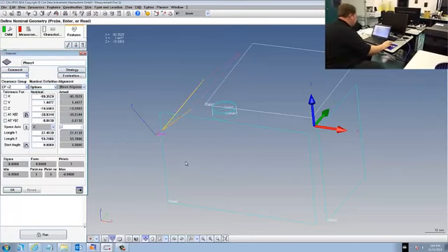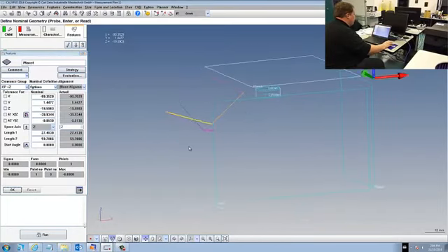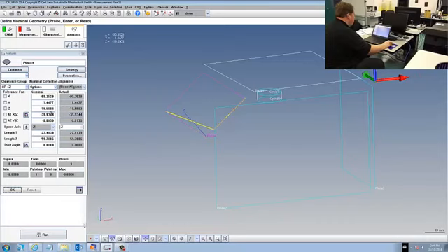In this particular case, the key item that we're correcting is the A1 and A2 angle, except this time these values are not 0. In some other software, these angles would be calculated with an IJK value. Then you would have to do a whole bunch of trigonometry to figure out exactly what to put here. Calypso makes this easy. This is a 40-degree face.